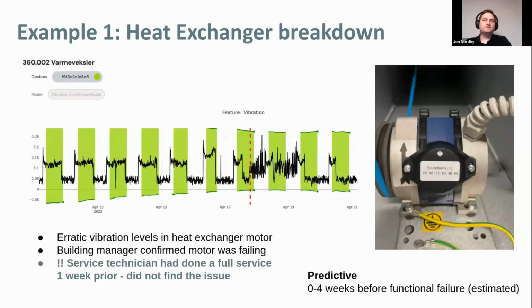Here are some examples from the real world, using production data. This was a heat exchanger motor that started to get erratic vibration levels around this red line in the center. An alarm was raised, and the building manager confirmed the motor was indeed failing. It hadn't stopped functioning yet but was very close to failing, and they were able to fix it before it completely failed, so there was no impact on the tenant.